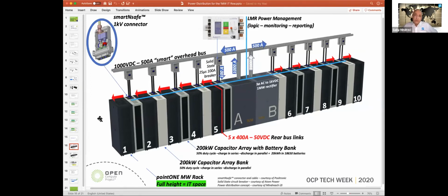And considering the standard rack size that's shown in this diagram has the ability to fit IT equipment, the IT gear here basically would require 100 kilowatts of power. So let's assume we have the gear that fits in the standard rack. Obviously, for the down conversion element, taking 1000 volts DC and converting it down to 50 volts DC to go into the IT equipment, we need to do that. And it's a huge challenge.